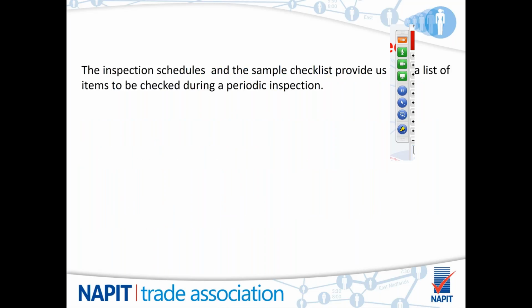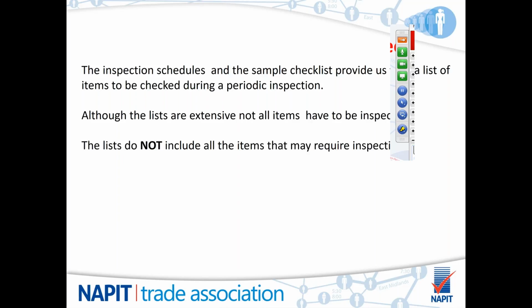The inspection schedules attached to the EICR, and sample checklists provided within Guidance Note 3, give us lists of items to be checked during a periodic inspection. Although the lists are extensive, not all items have to be inspected during a periodic inspection, and the lists do not include all items that may require inspection.